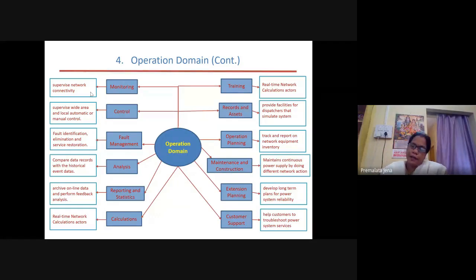This is how a monitoring platform helps in supervising the voltage profile and frequency profile at every load or generator terminal, which is essential. Then the operator can take preventive decisions beforehand. If somewhere a line or voltage is collapsing, a quick signal can trigger capacitor banks or dynamic DVRs to come on and take care of the voltage collapse. So monitoring helps in many aspects; once we monitor, we know where the flaws are in the network, and then further actions can be taken.